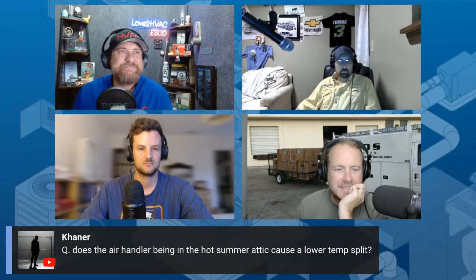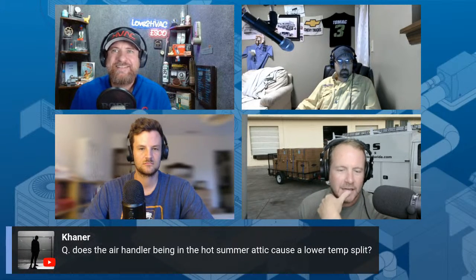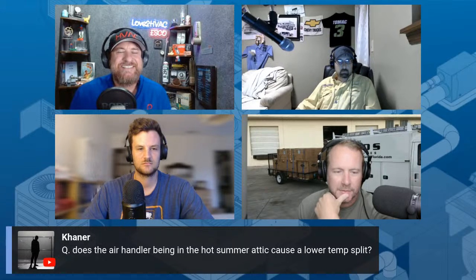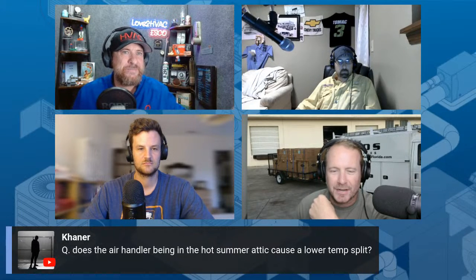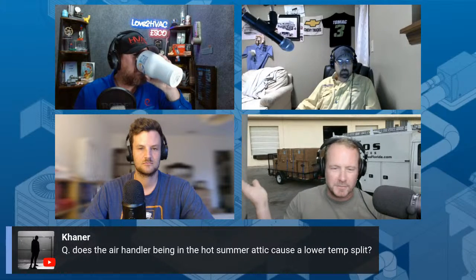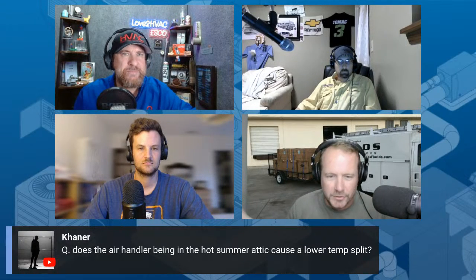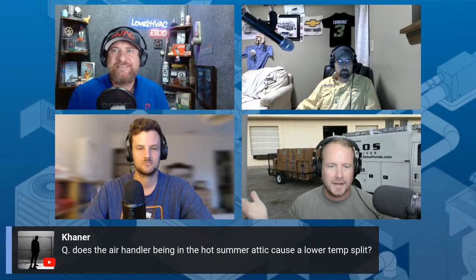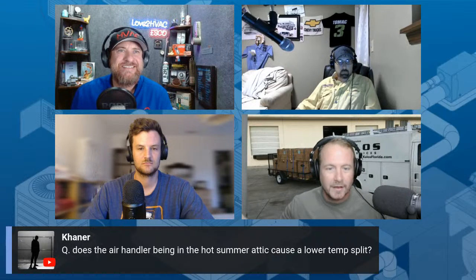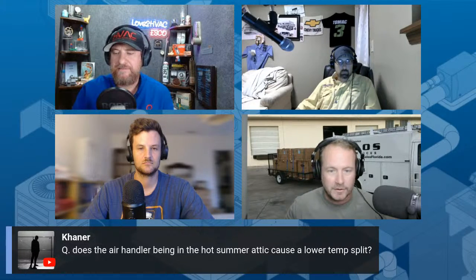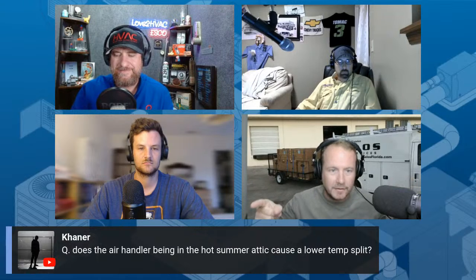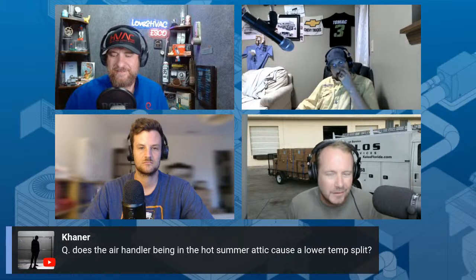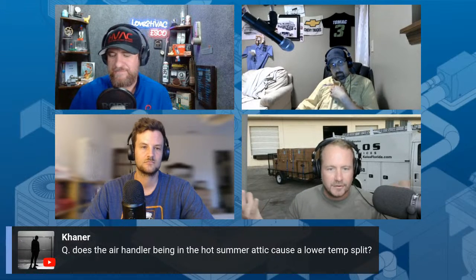All right, so does the air handler being in a hot summer attic cause a lower temperature split? I'll take this one right off the bat. Generally speaking, because both your return and your supply are in the hot summer attic, it depends on where you're measuring your temperature split. If you're measuring it at the return and supply grills, which I don't recommend unless you're doing both, then yes, it will affect that - it'll definitely decrease it. But if you're measuring it right at the equipment, right before it goes in and out, could it have a nominal increase just because of the heat on the cabinet? Maybe a little bit, but not generally - it's not going to be significant because they're both going to be affected. That's my thoughts on that.